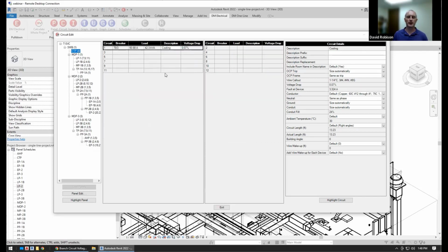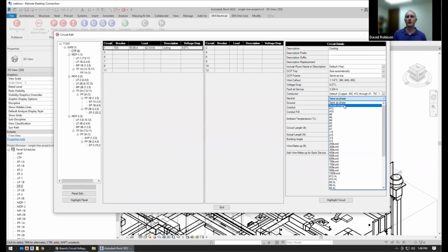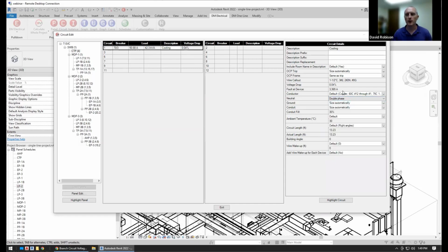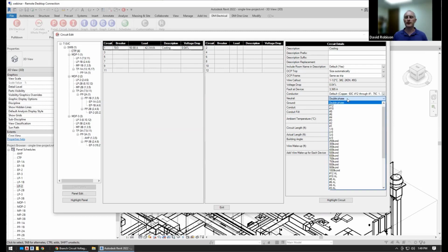So if we go over here to CTP and we double this neutral, we're going to end up with 5 wires rather than just 4. And there's actually a derating that needs to happen. So when you change this to a double phase, we will derate the wire and give you something slightly larger to account for that. So just be aware that if you go from same as phase to double phase and it's a 3-pole circuit, you'll actually get larger wires. And then again, you can choose a specific size for the neutral.